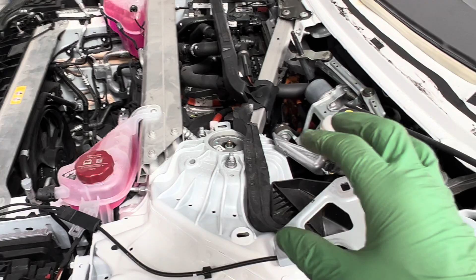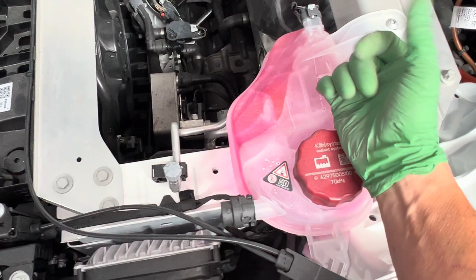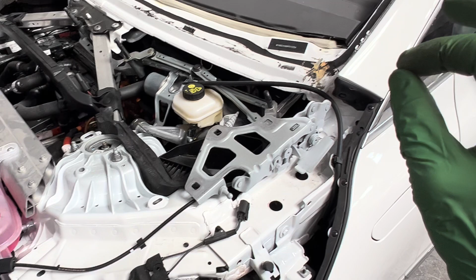You could get on the internet, look up this vehicle, and probably pull up the workings of how this HVAC system works, and also possibly the heat pump, and how they cool off the batteries in this system. I haven't read anything on this vehicle before. Is it a plate heat exchanger using that plate heat exchanger in the glycol to cool the back, or do they have a secondary direct expansion valve like some earlier BMWs had on their battery packs in the back? They had a line coming all the way back feeding liquid to another expansion valve directly connected to the hybrid high voltage battery to cool it off.